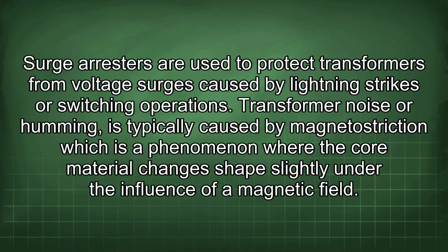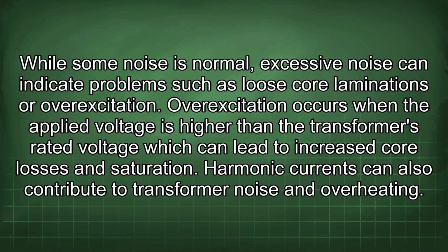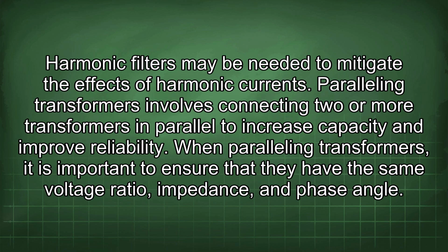Transformer noise or humming is typically caused by magnetostriction, which is a phenomenon where the core material changes shape slightly under the influence of a magnetic field. While some noise is normal, excessive noise can indicate problems such as loose core laminations or overexcitation. Overexcitation occurs when the applied voltage is higher than the transformer's rated voltage, which can lead to increased core losses and saturation. Harmonic currents can also contribute to transformer noise and overheating. Harmonic filters may be needed to mitigate the effects of harmonic currents.